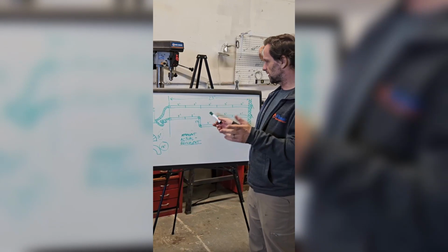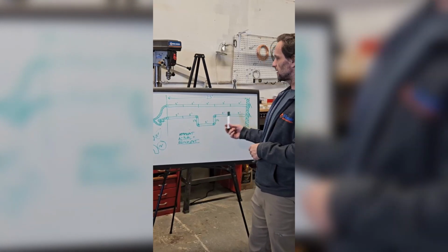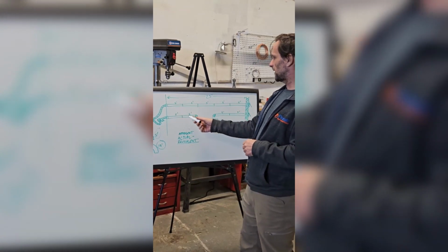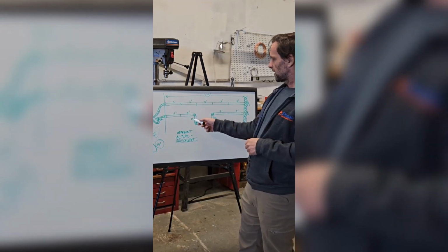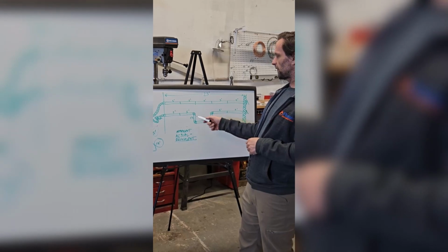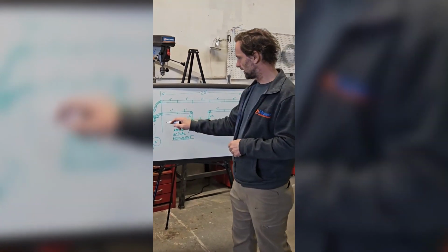This is when you actually find out, by whatever means, so you get to see the actual duct, and you know exactly what it's doing and where it's going. So the actual length here is, we know, 10, 20, 25. It's got these two short sections here, each 2.5 feet, so 5. So this run has an actual length of 30 feet, 5 foot longer than this one.